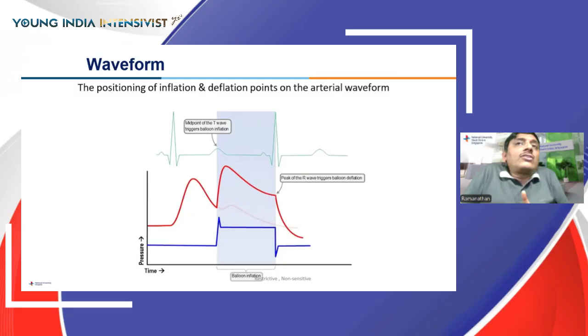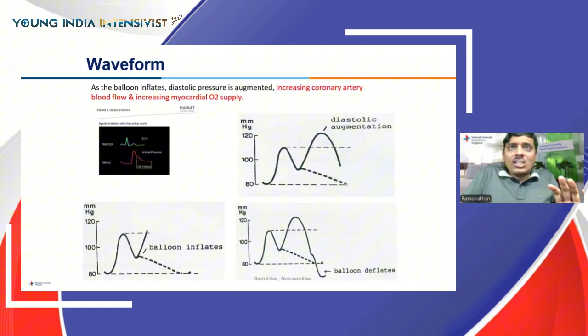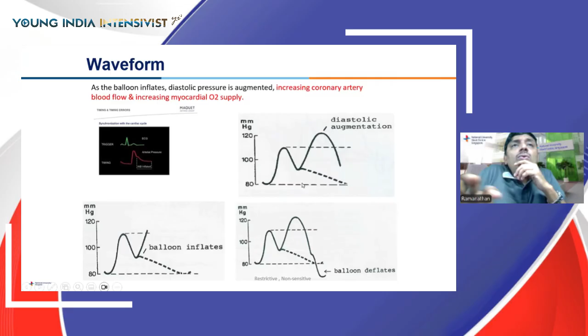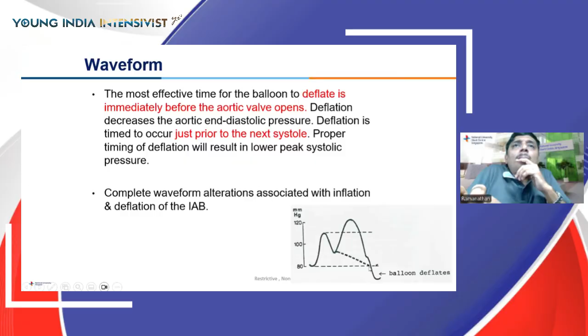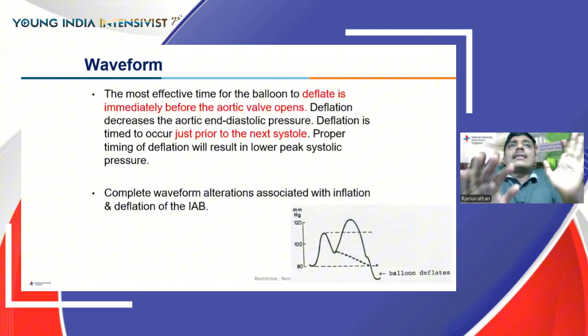So the midpoint of the T wave in the ECG triggers the balloon inflation, and the peak of the R wave triggers the balloon deflation. What it essentially causes, as we said earlier, is a diastolic augmentation right from the dicrotic notch, and the balloon goes on to deflate just before the aortic valve opens. So it decreases the aortic end diastolic pressure, and it's timed just prior to the next systole.